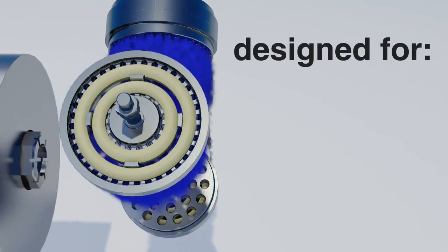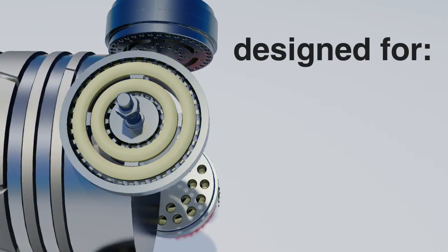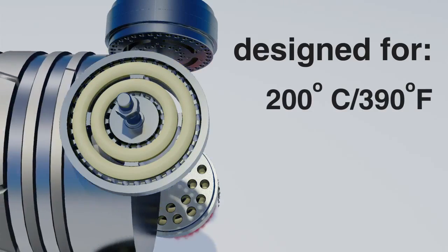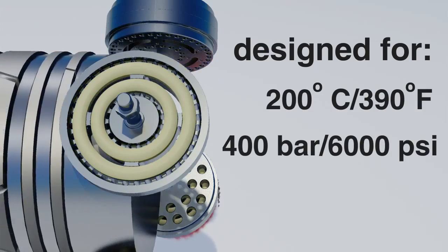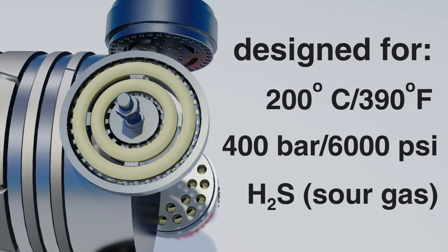The radiused disc valve from CPI is designed to operate reliably where temperatures exceed 200 degrees Celsius, 390 degrees Fahrenheit, pressures exceed 400 bar, 6,000 psi and with gas high in H2S or more commonly referred to as sour gas applications.